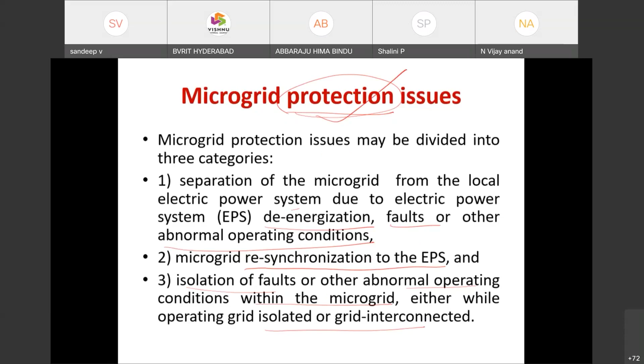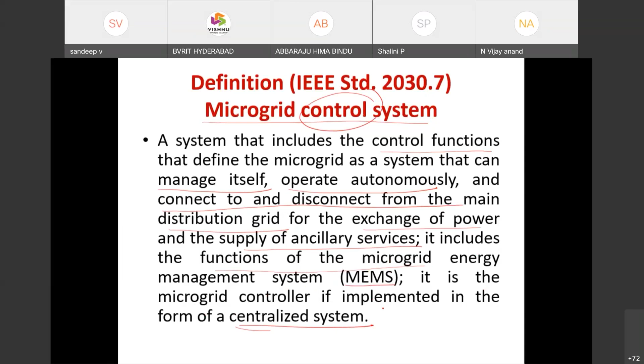There is a standard definition, IEEE standard 2030, for the microgrid control system. It includes the control function that defines microgrid as a system that manages itself, operates autonomously, to connect and disconnect from the distribution grid for exchange of power and supply of ancillary services. It includes the functions of the microgrid management system, MEMS, which should be implemented in centralized form as per this IEEE standard.